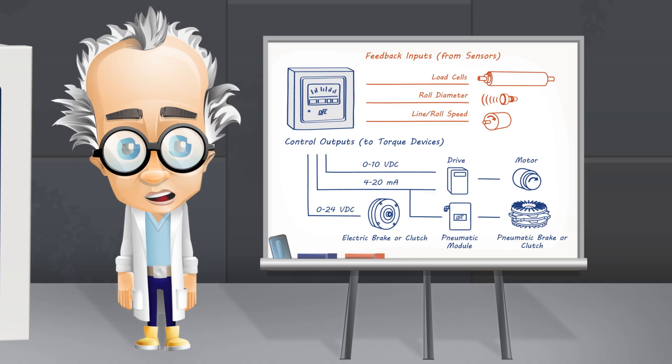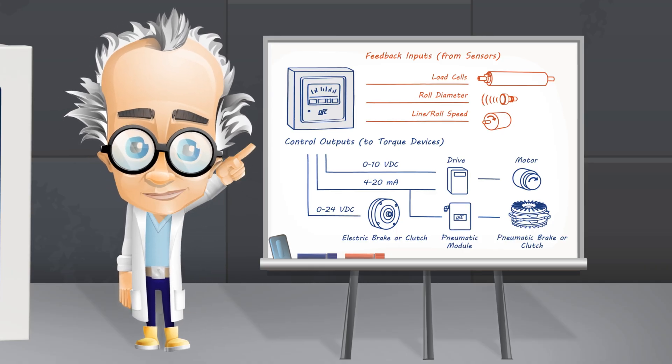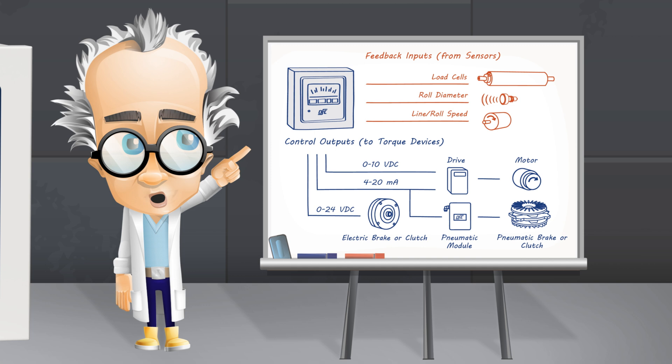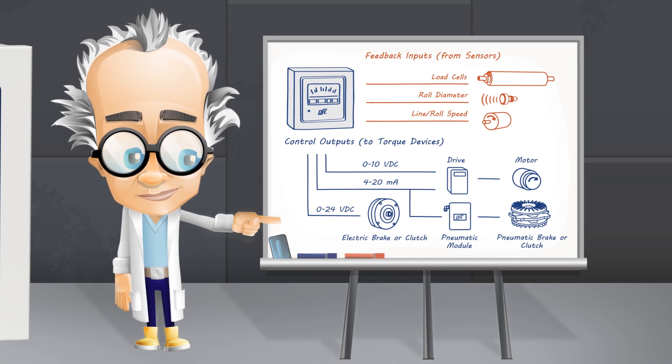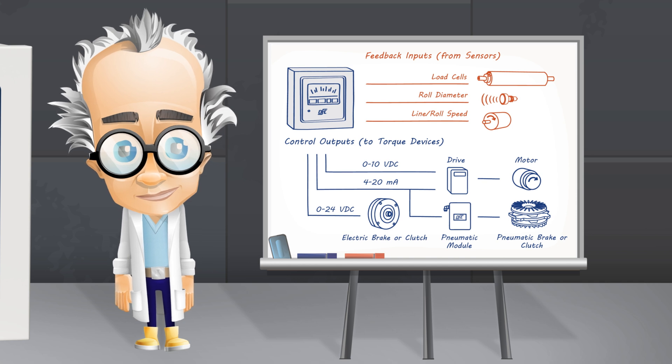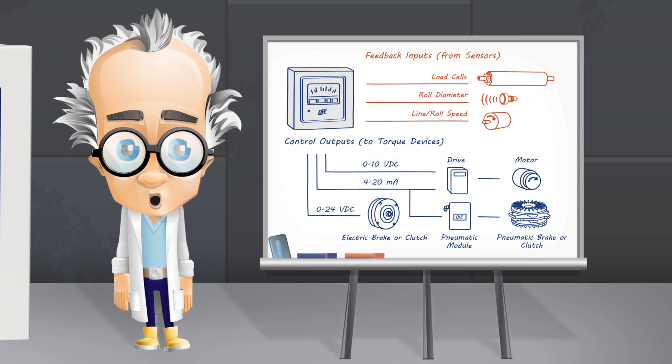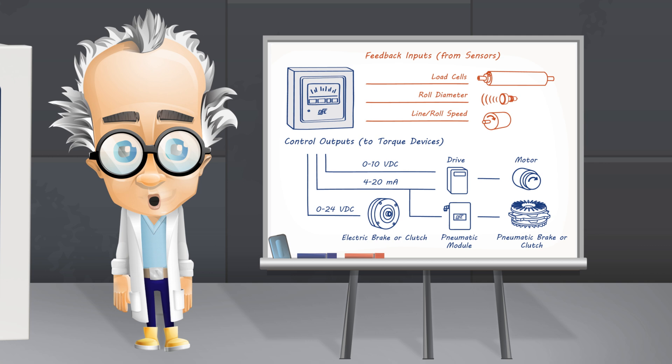The user selected set point is maintained by measuring web tension from a load cell and then sending a compensating signal to a tensioning device such as a pneumatic brake, clutch, or motor drive. The controller may be used in unwind, rewind, and intermediate tension zones.